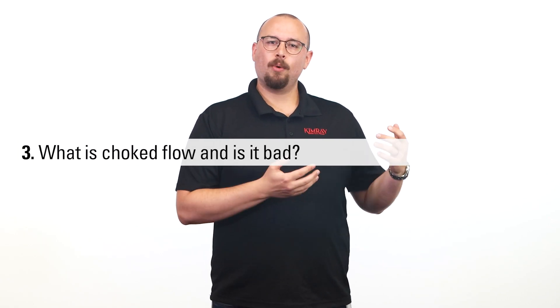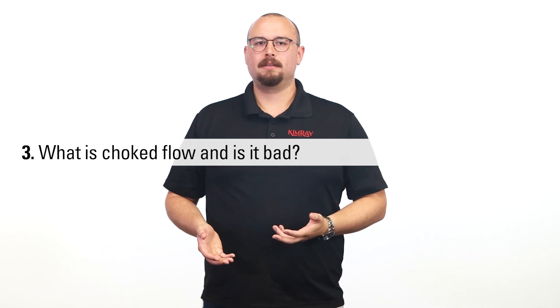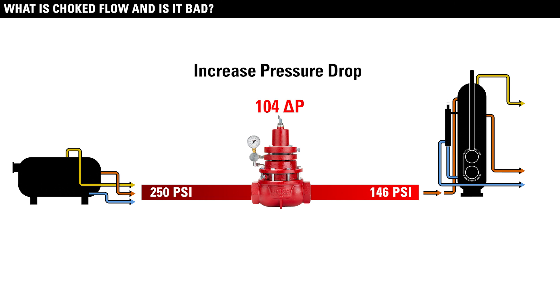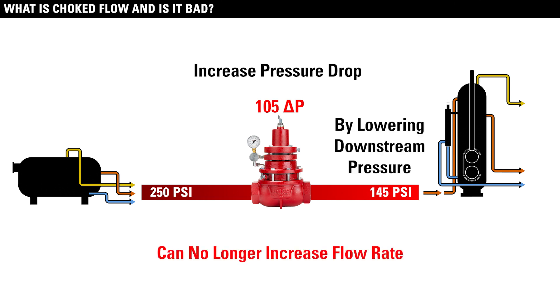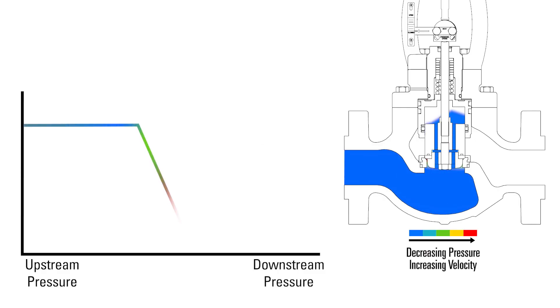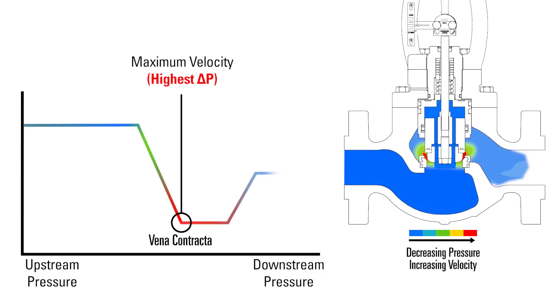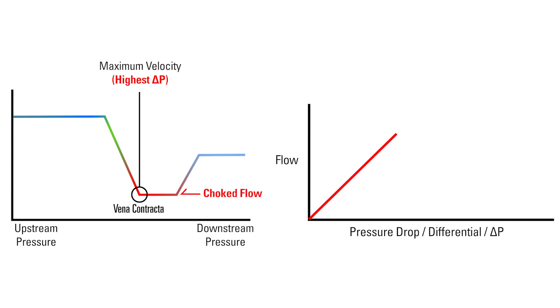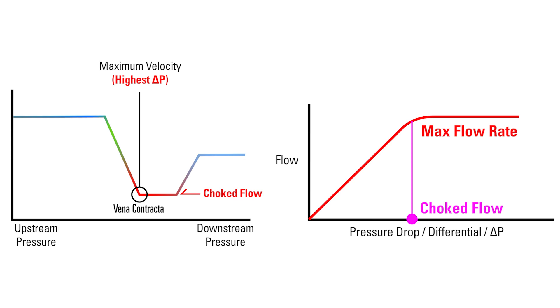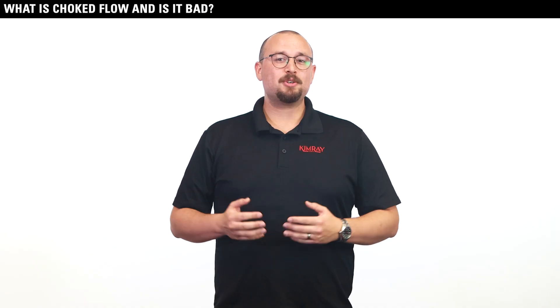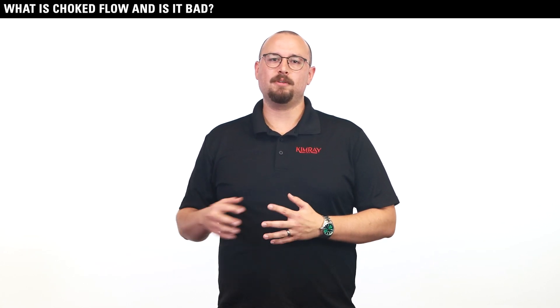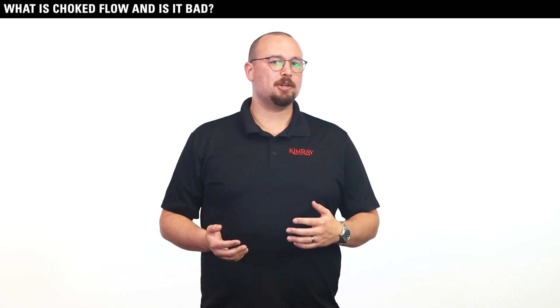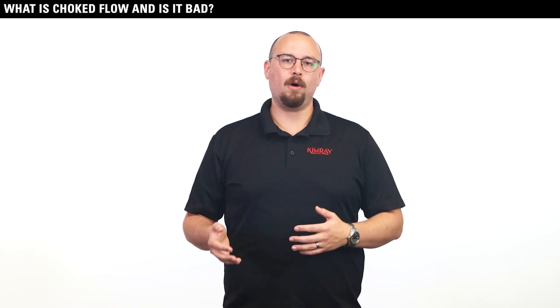Question three is related: what is choked flow and is it bad? There comes a point, if you're increasing the pressure drop by lowering the downstream pressure, that you're not going to increase the flow rate. The fluid will reach its maximum velocity at the vena contracta, and after that point it will enter a state called choked flow. The higher the pressure drop is, the more flow you can get across a given orifice size. If you want to increase the volume using the same valve and equipment but you have it in choked flow, you won't be able to. This creates problems because you can't pass the amount of volume you need, and depending on the application, you might be starving another piece of equipment that needs volume to operate correctly.